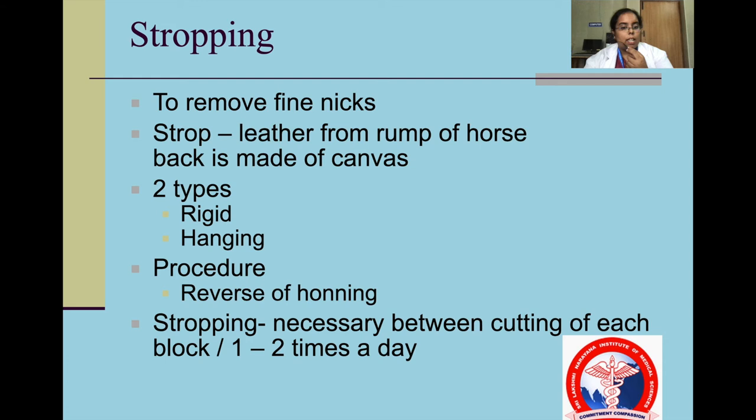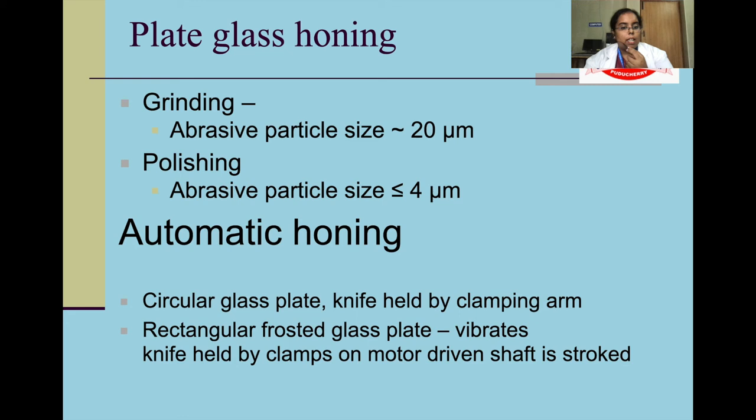Stropping is to remove fine nicks, using leather from the rump of a horse made into canvas. Two types are rigid and hanging. Stropping is necessary between each block, done 1 to 2 times a day. Another method is plate glass honing using abrasive particles. Automated honing is also available.